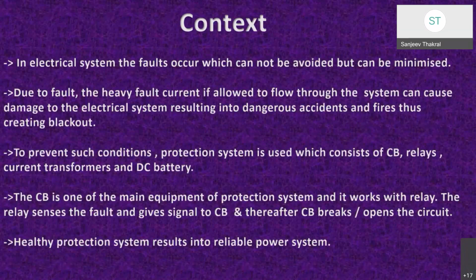In an electrical system, different types of faults occur which, if not addressed promptly, can cause damage to the electrical system, resulting in dangerous accidents and fire, thus creating blackouts. To prevent such harmful conditions, a protection system is used, which consists of circuit breakers, current transformers, relays, and a DC battery. The circuit breaker is one of the main equipment of the protection system. When a fault is diagnosed and signaled to the circuit breaker, the tripping coil of the circuit breaker gets energized, which allows the circuit breaker to open the circuit.